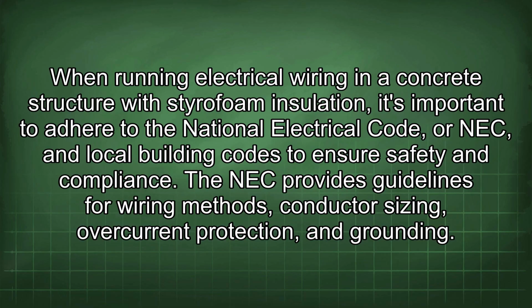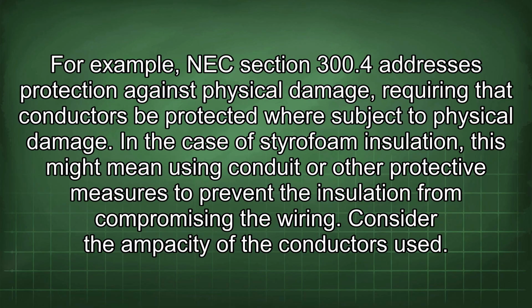When running electrical wiring in a concrete structure with styrofoam insulation, it's important to adhere to the National Electrical Code, or NEC, and local building codes to ensure safety and compliance. The NEC provides guidelines for wiring methods, conductor sizing, overcurrent protection, and grounding. For example, NEC Section 300.4 addresses protection against physical damage, requiring that conductors be protected where subject to physical damage.